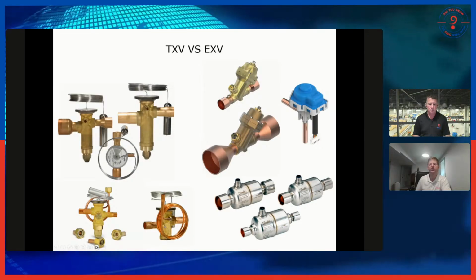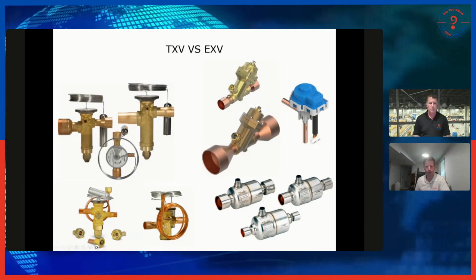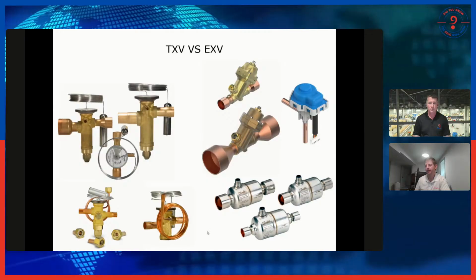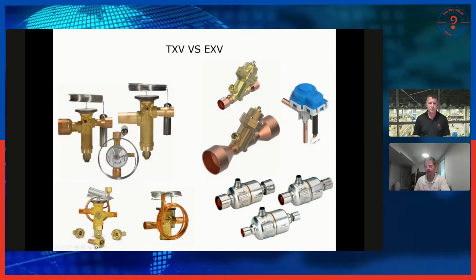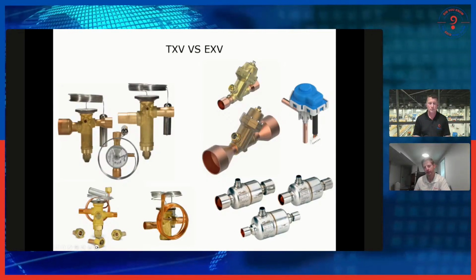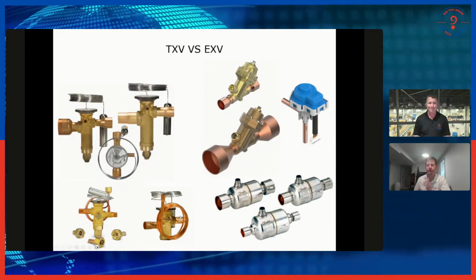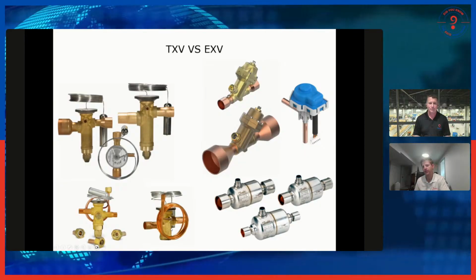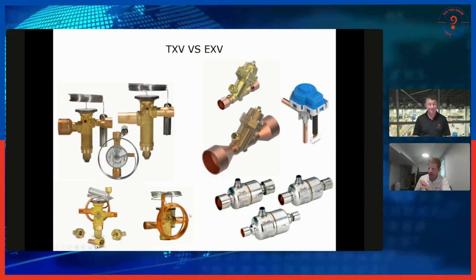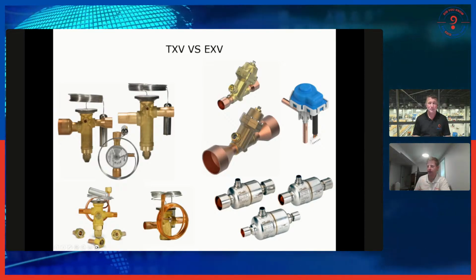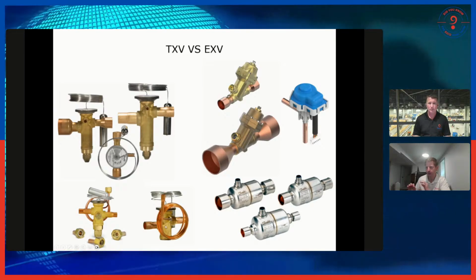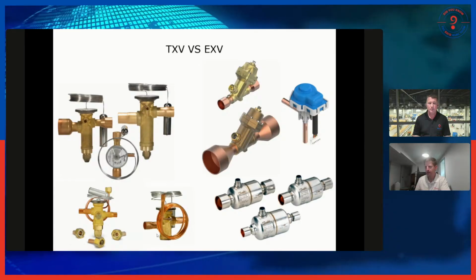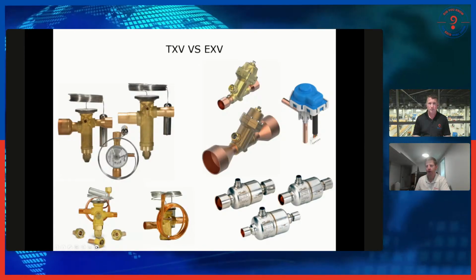The fixed setting ones are going to be used in the builder grade residential equipment, and that's because if we don't have that adjustment stem in there, it gets to be a little bit lower priced valve, and also the manufacturer knows no one can ever go through and mess with it. So a residential air conditioning manufacturer can figure out a setting in their lab that works good for their system, and they ship out a valve that's got no adjustment stem on it.